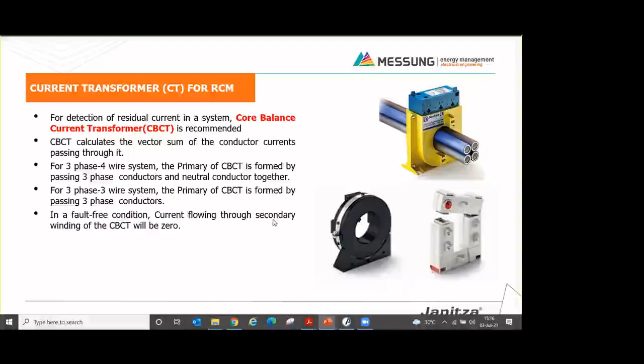It basically calculates the resultant of conductor currents flowing through it. In case of a three-phase four-wire system, the primary of the CBCT is formed by passing the three phases and neutral conductor together. And in case of a three-phase three-wire system, the primary is formed by passing the three-phase conductors. So how it works is, if the system is fault-free, then it will produce a secondary current of zero.